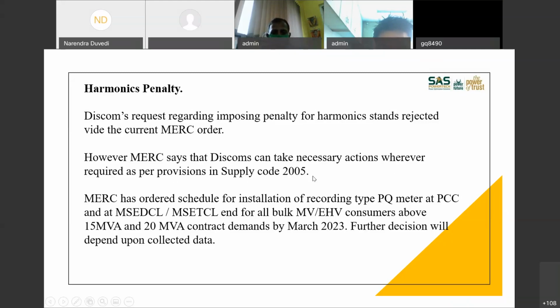So suppose I am in an organized industrial zone and I have a substation maybe 500 meters from me, and I know that my neighbor consumes more harmonic currents, and because of that I am getting some disturbances. Then I can go and complain to MERC, rather MSEDCL, and then if after checking they find that my neighbor is violating Supply Code 2005, then they can take action on him, or they can ask him to correct those harmonics, giving him some time limit or something like that. So that is still valid, but no penalty for harmonics on bills currently.